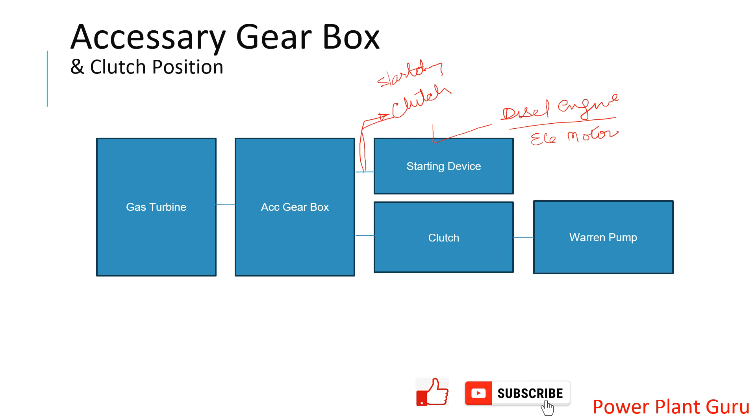After startup, the starting device gets disconnected and the gas turbine operates the accessory gearbox. This gearbox is a very large and complex equipment whereby all gas turbine accessories are driven through it. On this gearbox there is a shaft which drives the liquid fuel pump — in many GE gas turbine installations, a Warren-manufactured pump is used, so it is known as the Warren pump.